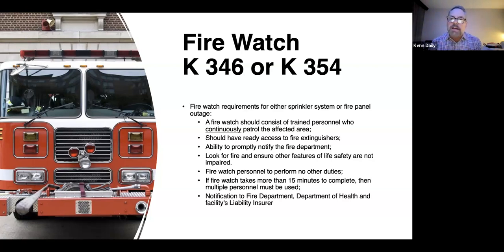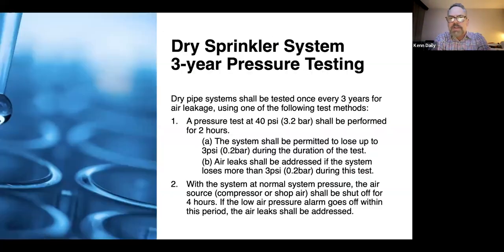They're just a human fire alarm watching for fire. Now, fire watch for a fire alarm being out starts no less than 4 hours after it's been out. And then for a sprinkler, it's 10 hours. The 10-hour mark was really allowing sprinkler companies to come in and do work on your sprinkler system, replacing pipe, which is very common and can take all day, but then they are not requiring you to be on fire watch when work is being done. So that's why your policy is slightly different. Same concept, fire watch either way. And you have notifications of the fire watch happening between your locals, your state fire department, your liability insurance company, and that type of thing.